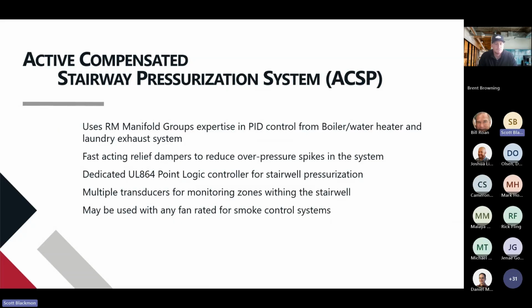So what did we do? We basically took our expertise from PID loop, from boilers, water heaters, all of our laundry room systems, and we created a dedicated system. We called it the Active Compensated Stairwell Pressurization System. I dare you to say that 10 times fast, so we call it the ACSP for short. But one of the nice features about the ACSP, first and foremost, is that it can be paired with any fan out on the market. As long as that fan is smoke rated, we can pair this control system with it and it works.